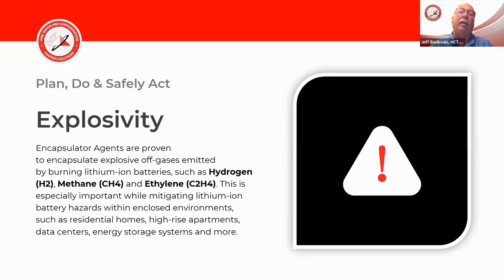Hydrogen gas created an explosive atmosphere. The system inside did little to nothing to cool things down. So when the doors were opened, air was introduced into the tank. We hit the proper air-fuel mixture, we had all the hydrogen, we had the heat, and we had a huge explosion, which caused these injuries to the firefighters.